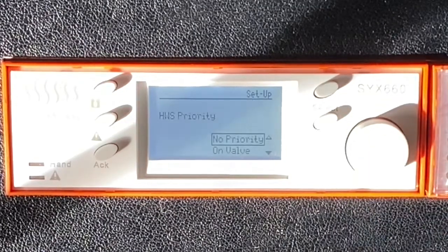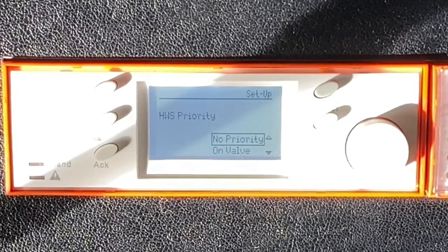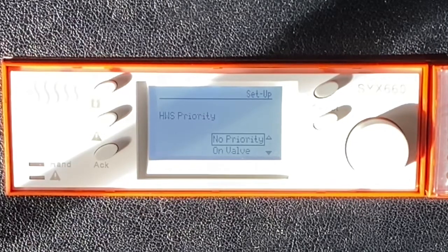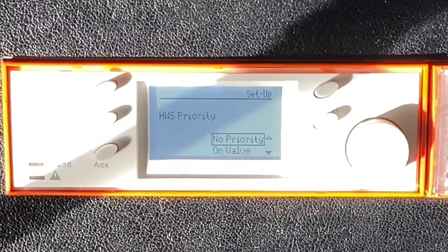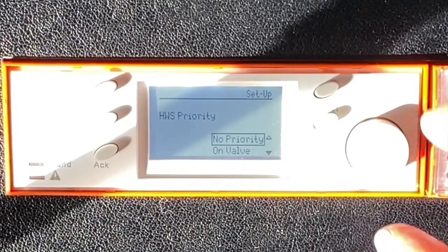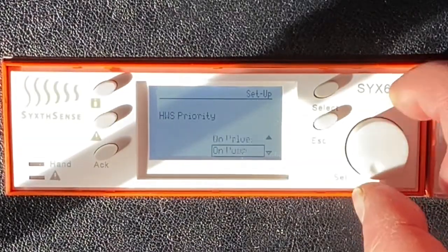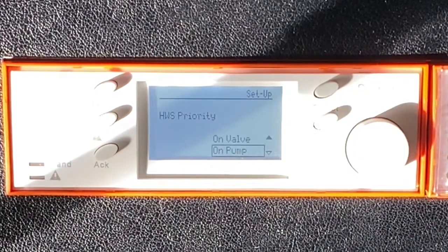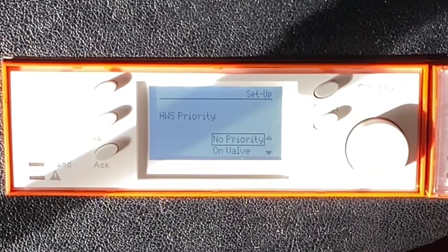HWS priority, if you have hot water plants serviced by the boilers, and the boilers are maybe a little bit undersized for heating the hot water jointly with a full demand of heating during the colder winter months, then we can take a decision to throttle back the heating supply and give priority to the hot water. And we can choose how we go about that by closing the valve down, or we can turn the heating pump off. So we choose which event we would like to do.